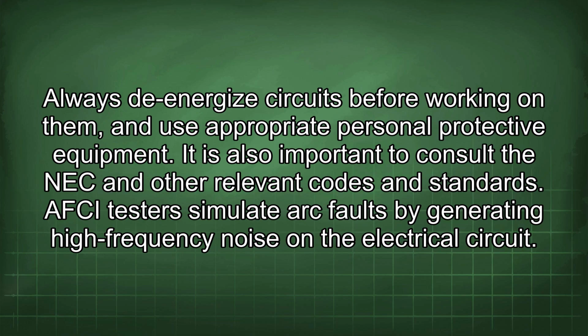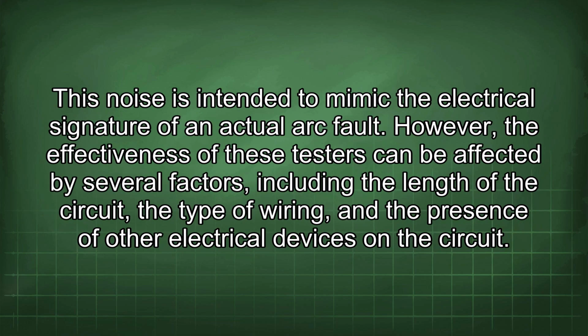AFCI testers simulate arc faults by generating high-frequency noise on the electrical circuit. This noise is intended to mimic the electrical signature of an actual arc fault. However, the effectiveness of these testers can be affected by several factors, including the length of the circuit, the type of wiring, and the presence of other electrical devices on the circuit.